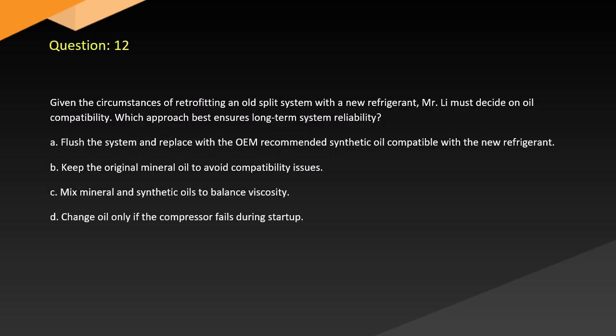Question 12. Given the circumstances of retrofitting an old split system with a new refrigerant, Mr. Li must decide on oil compatibility. Which approach best ensures long-term system reliability? A. Flush the system and replace with the OEM recommended synthetic oil compatible with the new refrigerant. B. Keep the original mineral oil to avoid compatibility issues. C. Mix mineral and synthetic oils to balance viscosity. D. Change oil only if the compressor fails during startup.